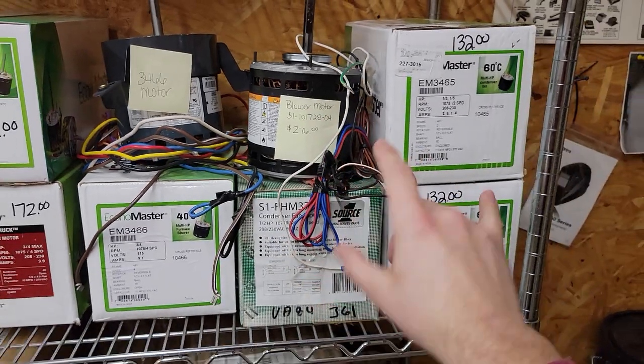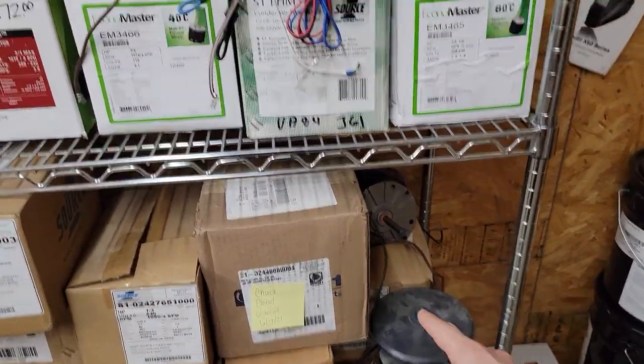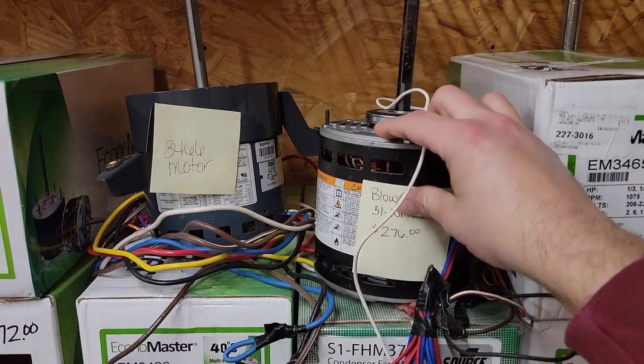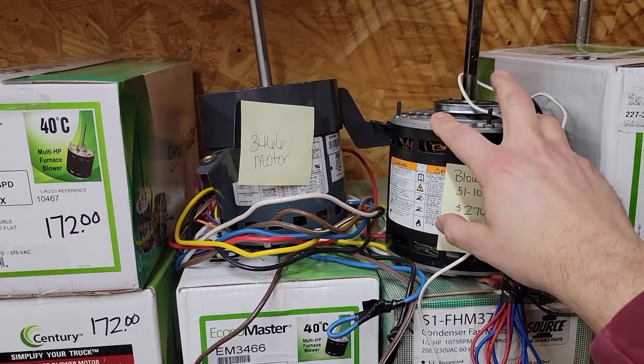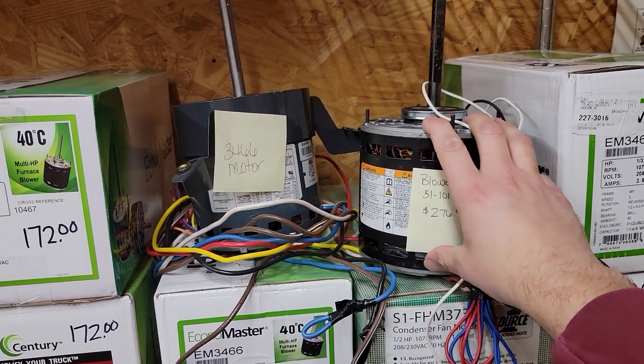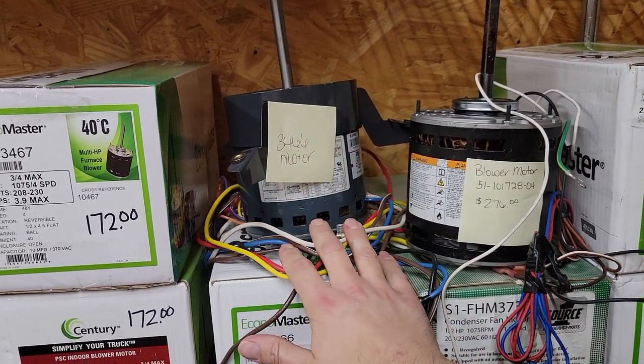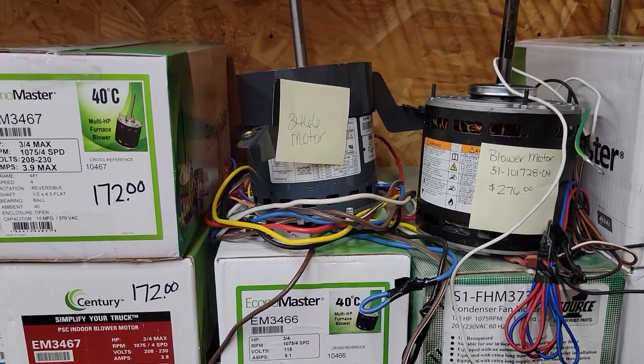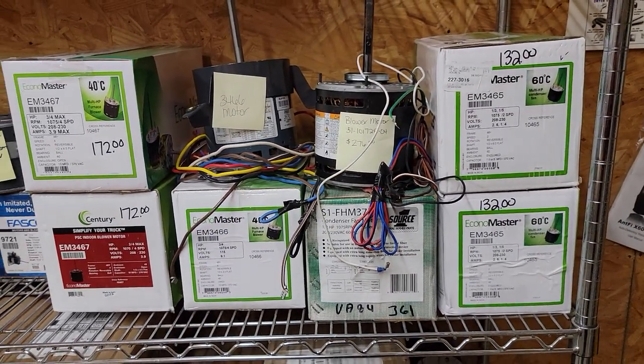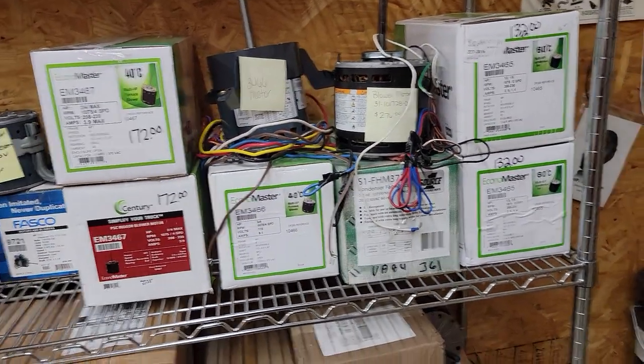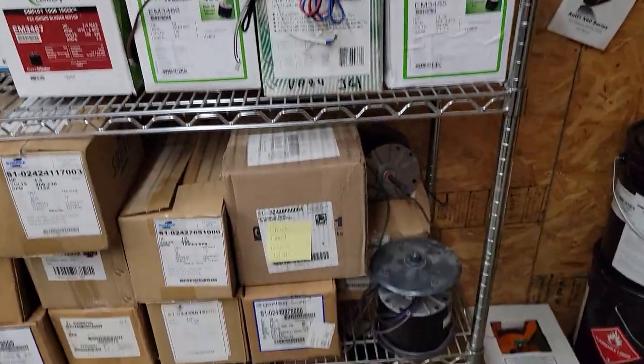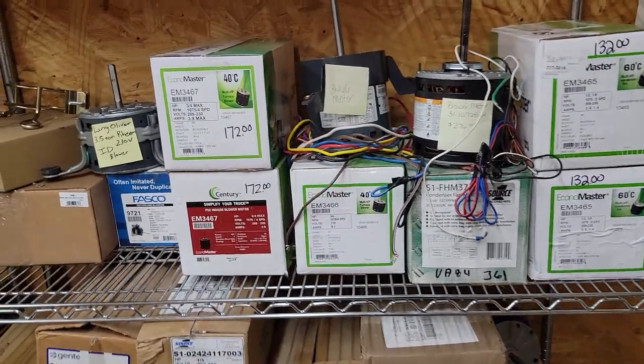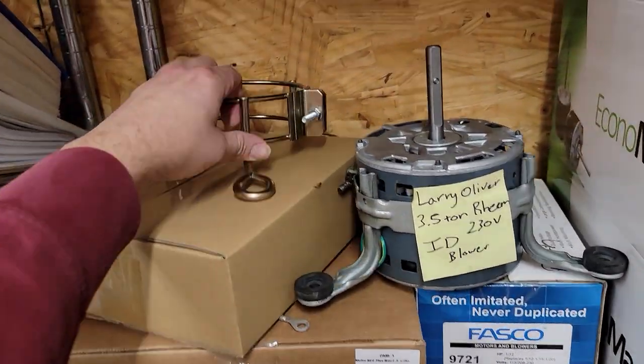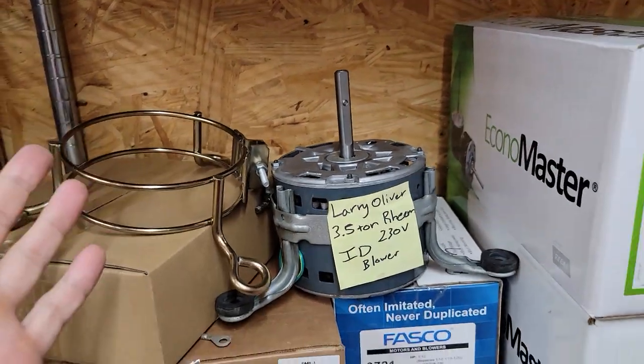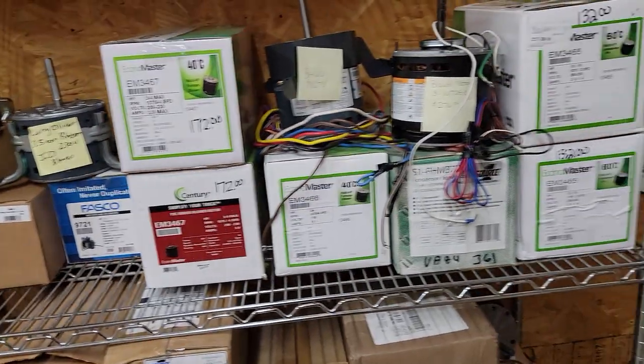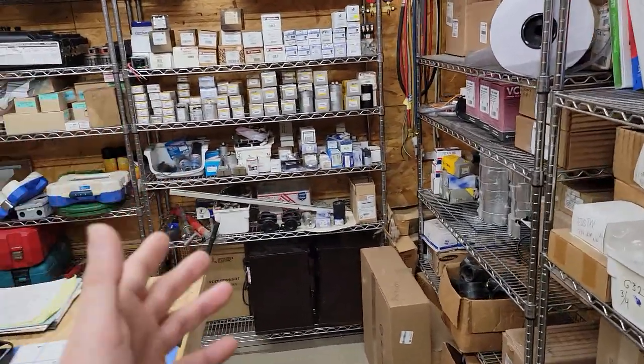You want to know more about motors? I've got a video on that. HVAC tips for technicians. It's a playlist. Check it out. So this right here is an indoor motor. You have 230 volt, which goes on heat pumps, split or package. And then you've got 115 volt, which goes on gas furnaces. And those are two different types of motors, but that's something you have to replace and you have to keep on your van. Definitely keep all three of those types of motors on your van. And if you want to learn more, again, check out my playlist. Brackets. You may want to keep motor brackets, because sometimes you'll have a motor's bracket just break, okay? So you got to keep motors, you got to keep capacitors, you got to keep contactors.